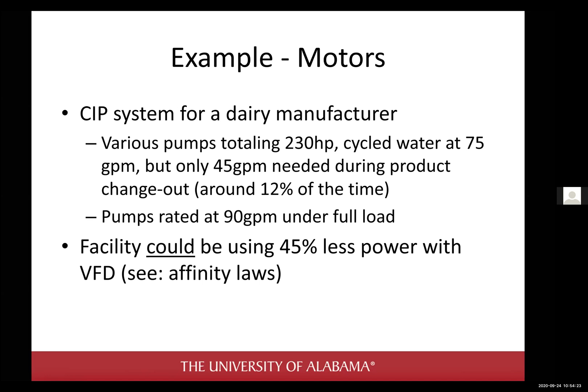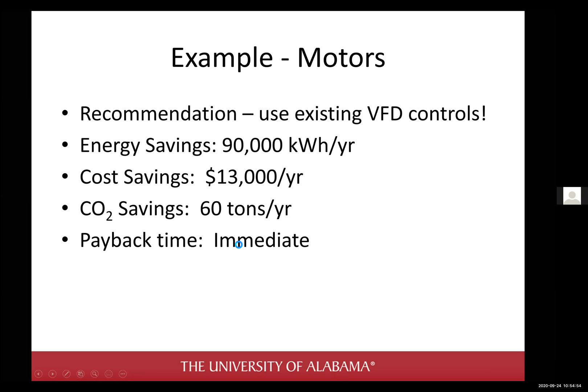on using these motors. So this is all just a big, long, drawn-out example to tell you that if you can use a variable frequency drive to run things at half or quarter speed when you need to, please do so. You can save a lot of energy, and it'll pay for the VFD. They're getting a lot cheaper these days. So, CO2 savings, 60 tons a year, immediate payback time. This was a win-win. Okay, so I'm going to spend 5 minutes talking about natural gas now.